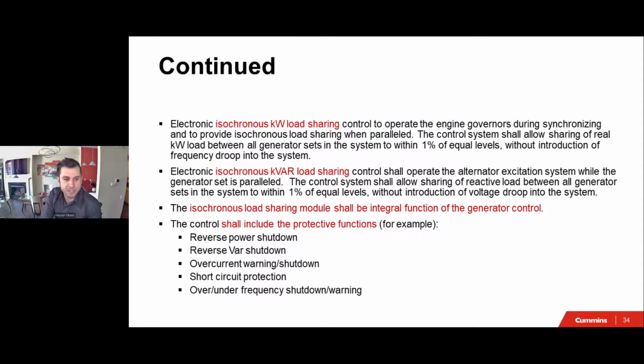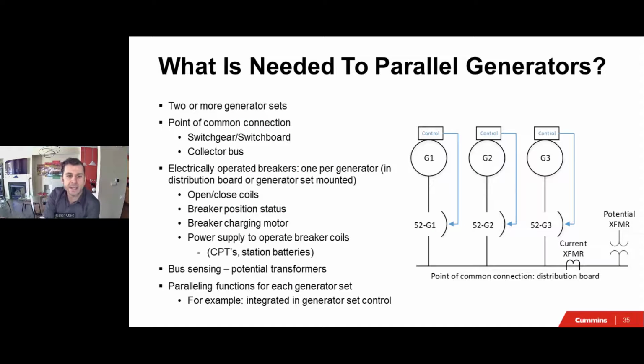paralleling generators. So to summarize it again, what is needed to parallel generators? To parallel generators, obviously we need two or more gensets. We need a point of common connection. That's it. This is the point where the power cables from the gensets are connected. And that could be a collector bus, or it could be a distribution board, and it's either a switchgear at UL1558 or a switchboard at UL891.